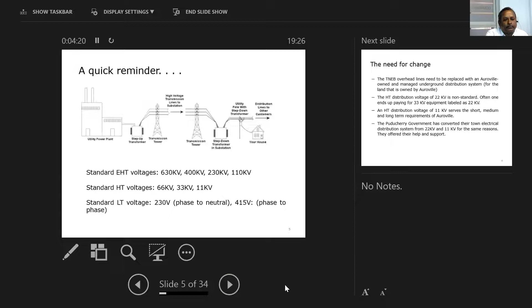Actually, we were one of the earliest supply restorers in this area, before Cuddalore and Pondicherry. Quick reminder: this is the EHT voltage: 630 kV, 400 kV, 230 kV, and 110 kV. And standard HT voltages are 66 kV, 33 kV and 11 kV. And standard LT voltage is 230 volts phase to neutral and 415 volts phase to phase.